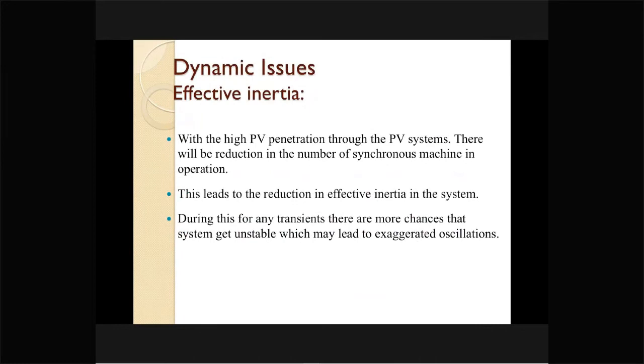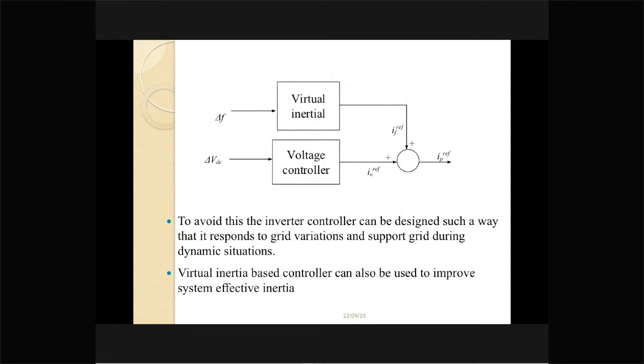Besides that, when the photovoltaic penetration becomes more and more, the inertia of the grid becomes less and less, and hence the net, effective inertia of this system reduces. Hence, we must do something with the photovoltaic integrated system at least, so that it produces virtual inertia. To get the virtual inertia, we produce the real power component of current from the change in frequency, and the first derivative and second derivative can be added here, such that this real power component of current will be proportional to that, and I can get a virtual inertial response.